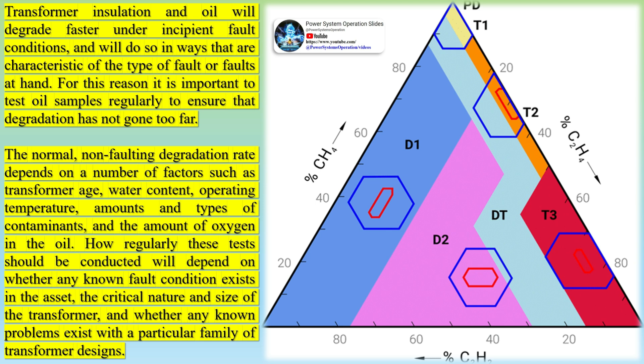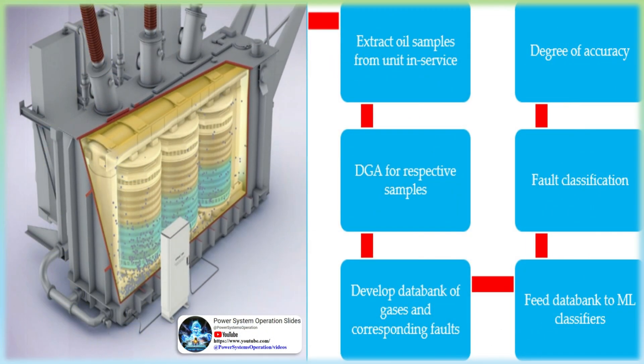Why should we implement DGA monitoring on power transformers? Dissolved gas is a leading indicator of the health of a transformer. Dissolved Gas Analysis (DGA) helps determine the types of abnormal events that may be occurring within the main tank. It is an effective way to analyze partial discharge, arcing, excessive thermal conditions, and more.